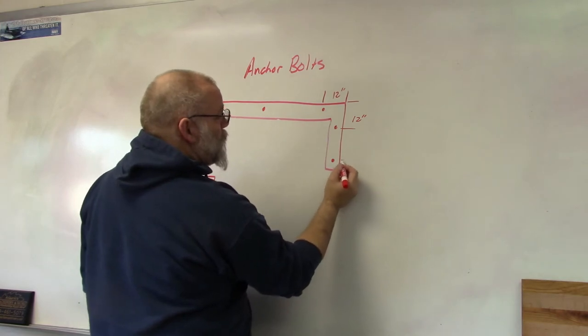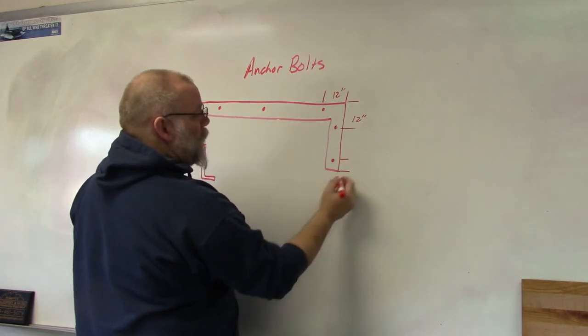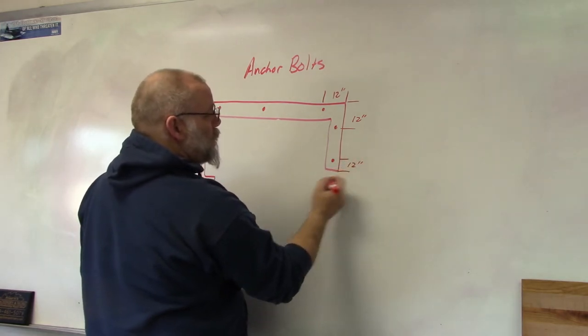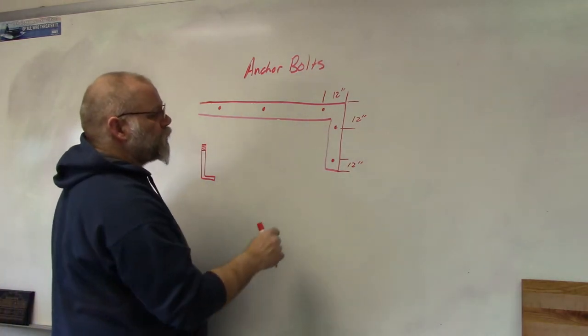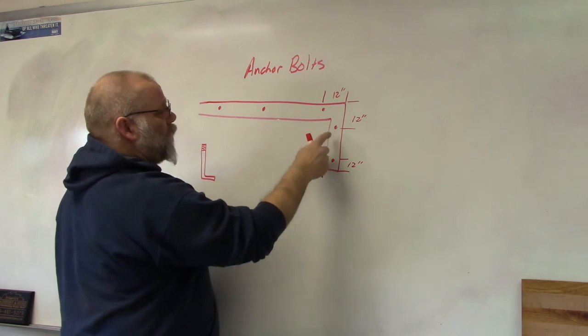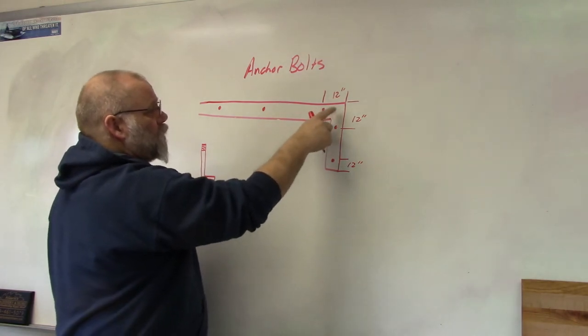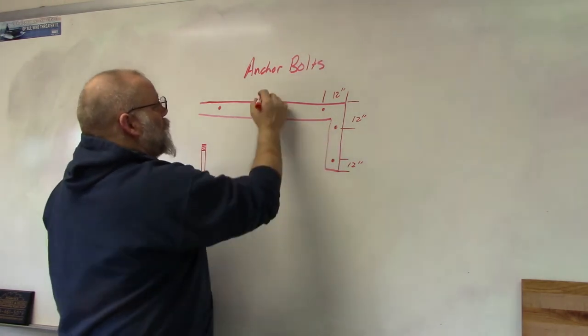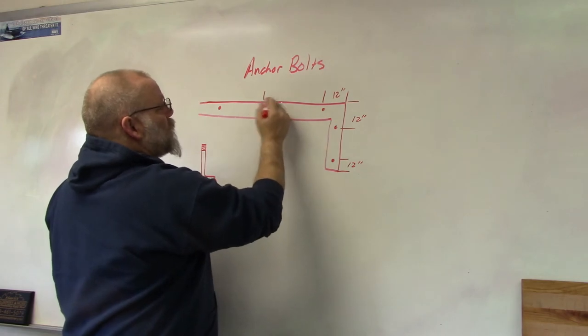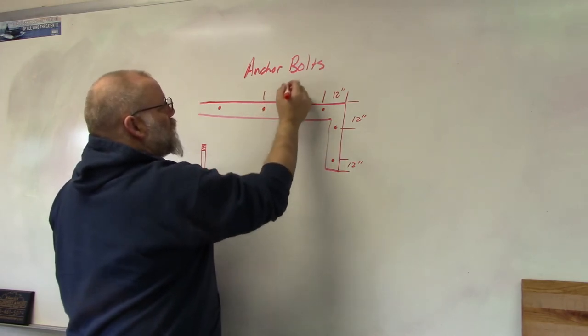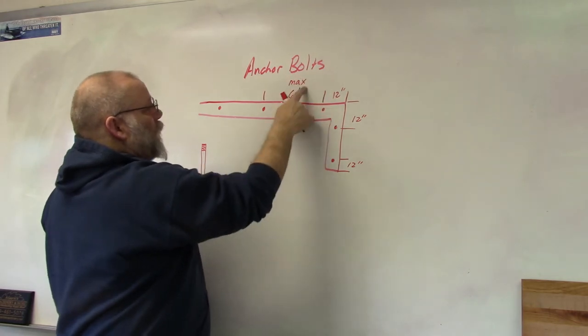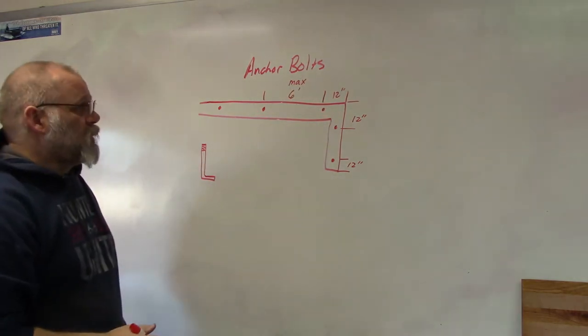You have to have one within 12 inches of the end of a wall. So 12 inches from the end of the wall, 12 inches in either direction of a corner, and the maximum distance from one anchor bolt to the other anchor bolt is six feet. So the max is six feet.